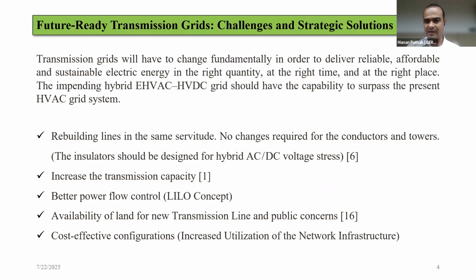We all know that right now the biggest concern in implementing a new transmission line is right of way. It's a big hurdle. So rebuilding the transmission line within the same servitudes means no change in required conductors and towers, though the insulator should be designed for hybrid AC-DC transmission as per the requirement and ratings. We'll look at a case study to justify that.